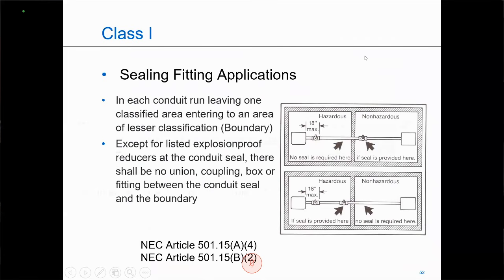So here we see a pictorial where the boundary seal is located on the non-hazardous side and one where it's located on the hazardous side. Providing that I meet my criteria within 18 inches, no other fitting except for the reducer, I'm in good shape with both of those as far as being a proper installation.